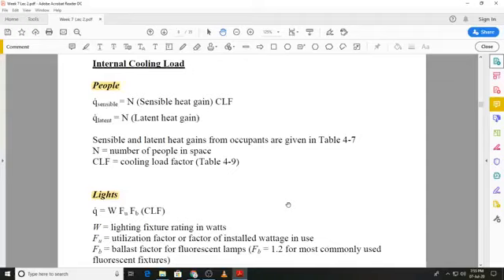For example, if we have lights which have a total wattage of 4000 watts and we are using 3000 watts out of those 4000 watts, then the usage factor or the utilization factor will be 3 by 4 or 0.75. If it is not given to us, we will assume that all the lights are being used and the utilization factor value will be taken to be 1 by default if it is not given to us. FB is the ballast factor, and that is for light fixtures in which you have any additional component which produces extra thermal load, and if again that is not given to us, we will use a FB value of 1.0.